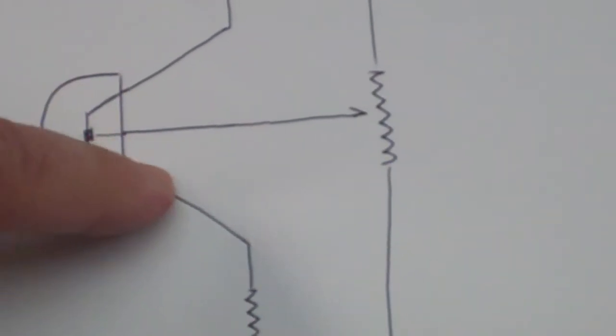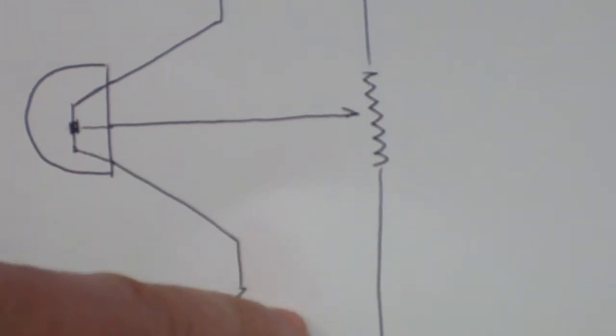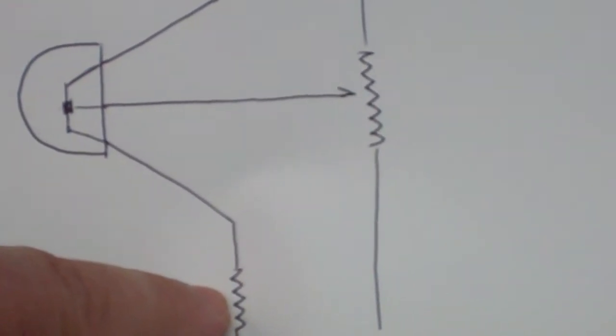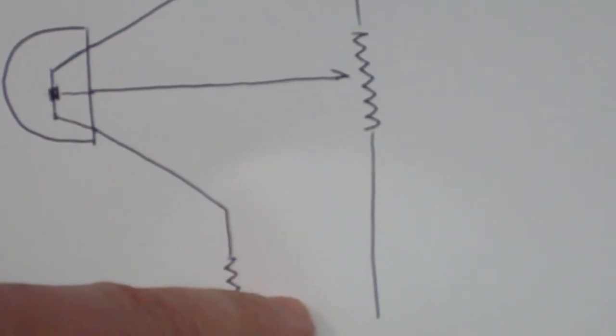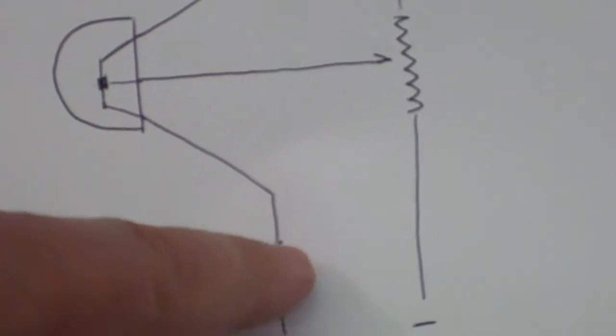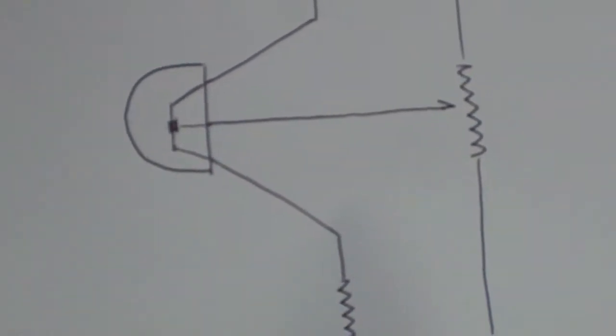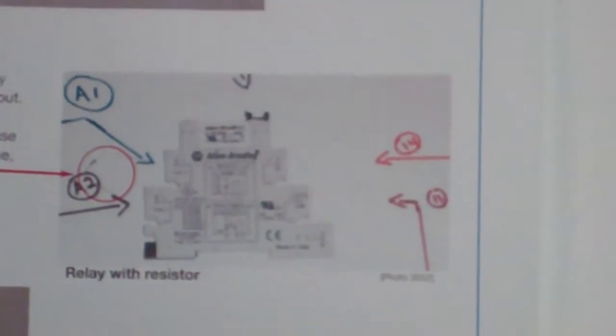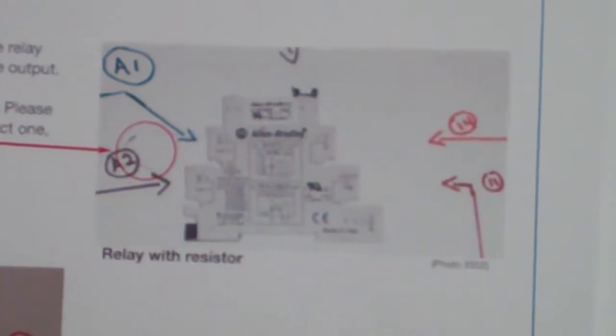So the leakage current goes through another resistor, bypassing the load. It has to be a very low resistance resistor to avoid other problems, but a shunt resistor solves a problem, and this did cause a problem for us in the field.